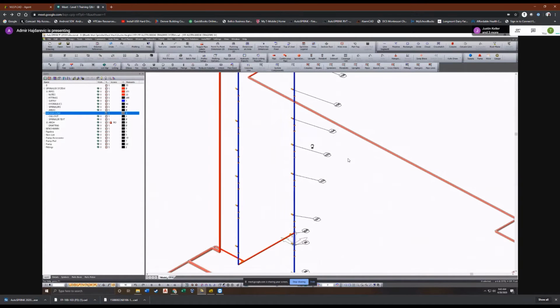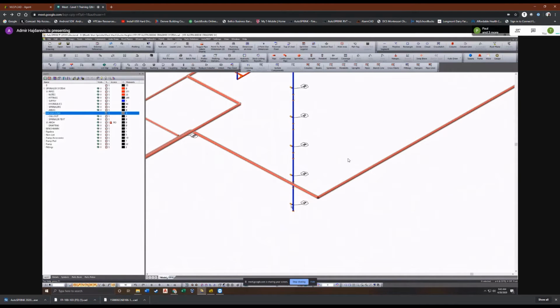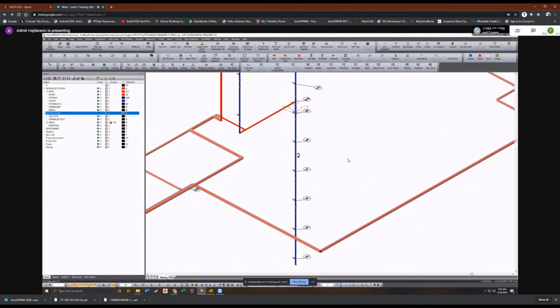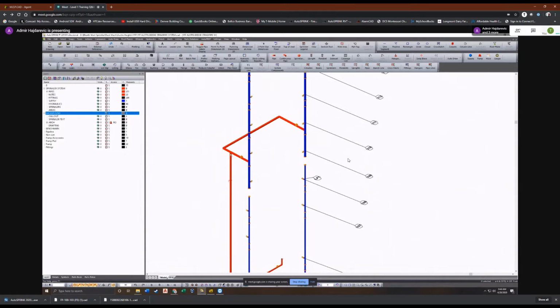However, is there any way to show the pressures for the lower end of the standpipe? They're not showing up. Actually, wait, that's a bigger question on its own. Let's just stick to high pressure for now. I have two pressure zones, right? This is my high pressure. Sure. Understood. High zone, low zone. I got you. It's not picking up this hose valve.